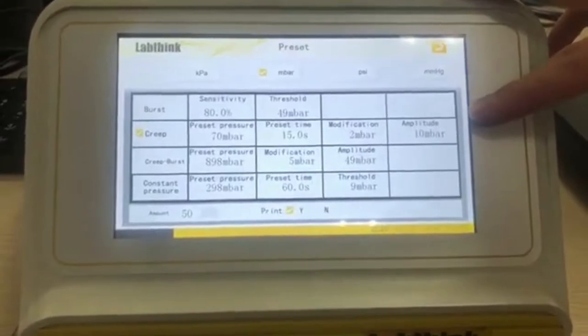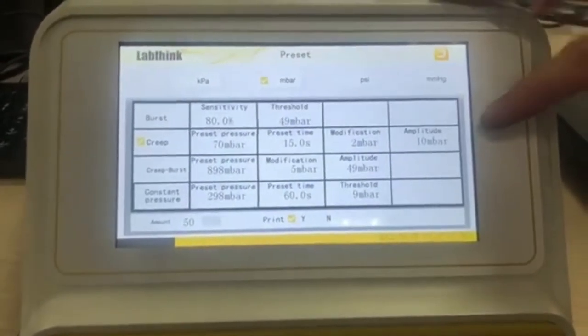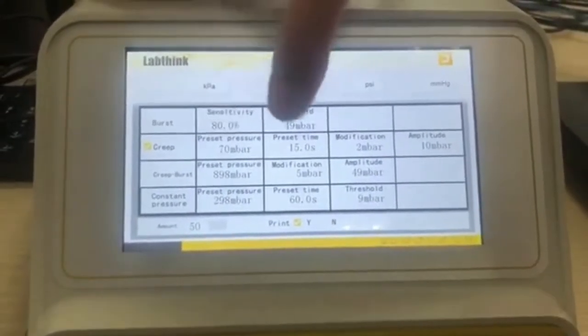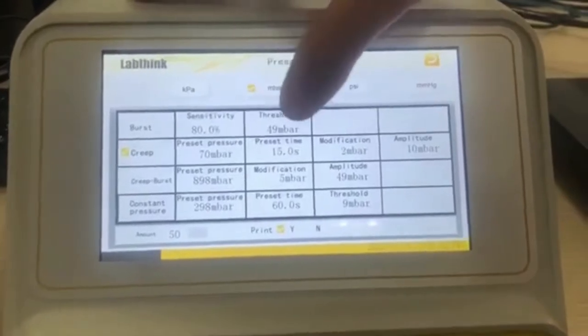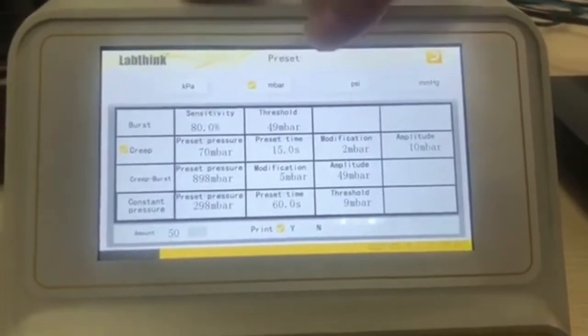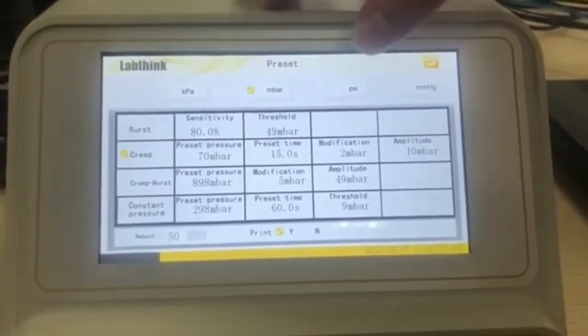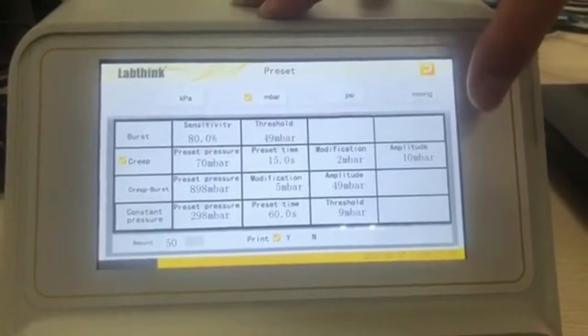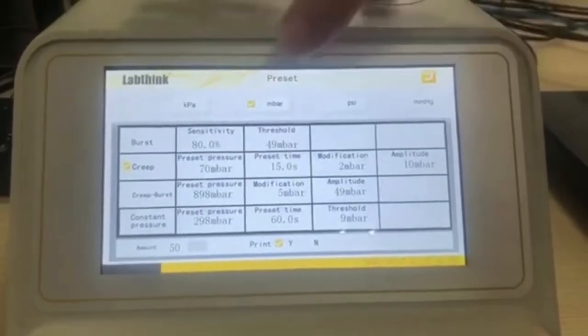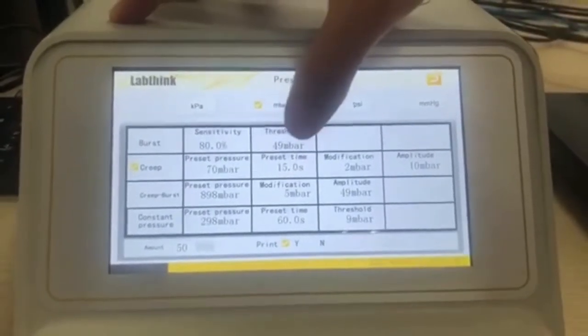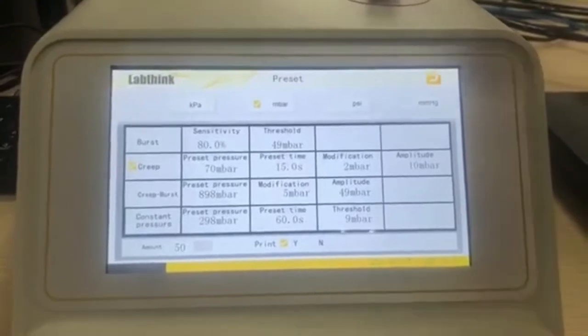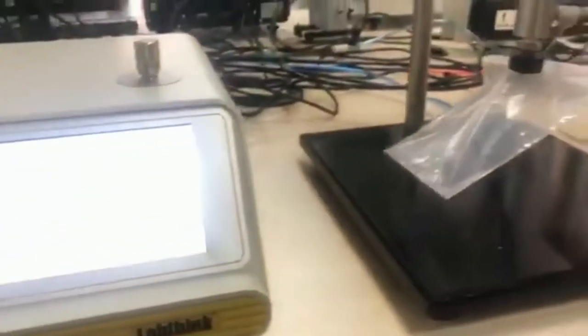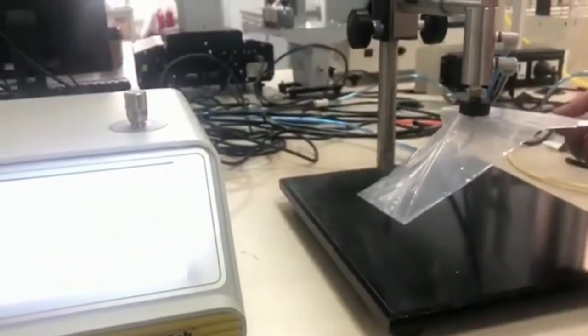It is allowable preset decay from the preset pressure in this time. For example, if the pressure decay is over 10 millibar in 15 seconds, the pouch will be considered as a disqualified one.